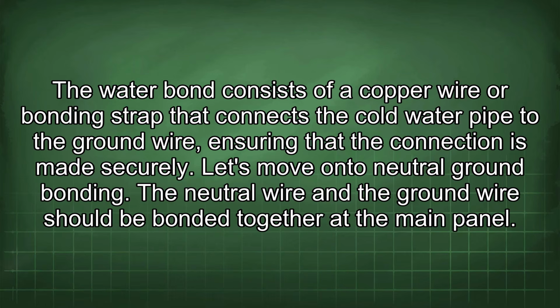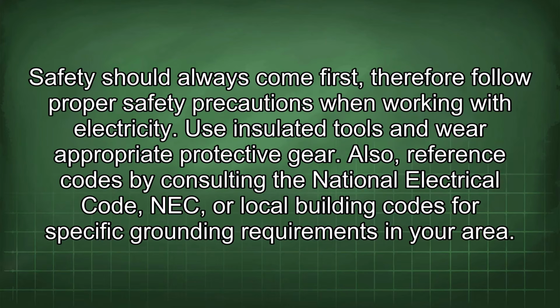Let's move on to neutral ground bonding. The neutral wire and the ground wire should be bonded together at the main panel. Safety should always come first, therefore follow proper safety precautions when working with electricity. Use insulated tools and wear appropriate protective gear.